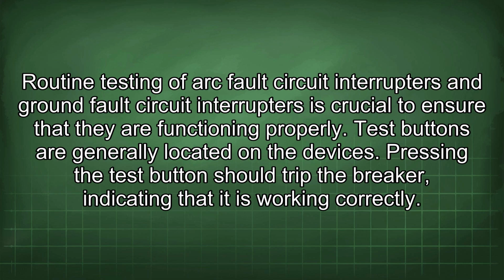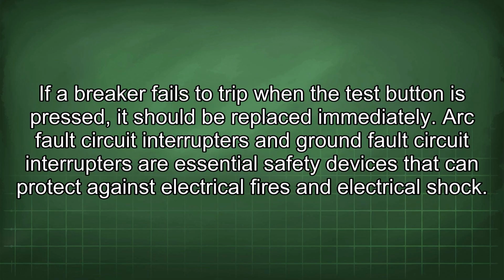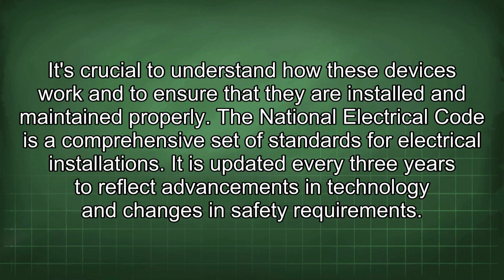Pressing the test button should trip the breaker, indicating that it is working correctly. If a breaker fails to trip when the test button is pressed, it should be replaced immediately. Arc fault circuit interrupters and ground fault circuit interrupters are essential safety devices that can protect against electrical fires and electrical shock. It's crucial to understand how these devices work and to ensure that they are installed and maintained properly.